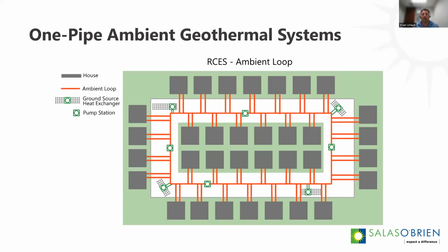Just to give you an example, this is what a single pipe design would look like diagrammatically. I don't know too many communities laid out this way, but it shows you can place energy sources in different locations at smaller scale, interconnect all the homes, and use a couple of smaller pumps to move fluid around the community, injecting or rejecting energy depending on the season at strategic locations. We're still accounting for diversity and the heat transfer of the pipe, but now we have resiliency because we have more than one location for the ground loops.